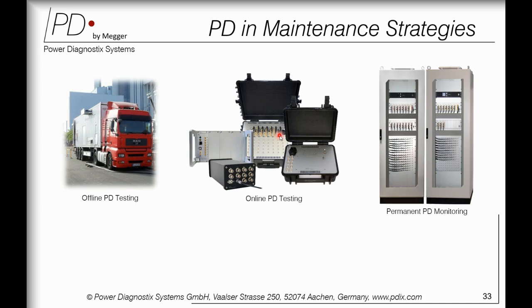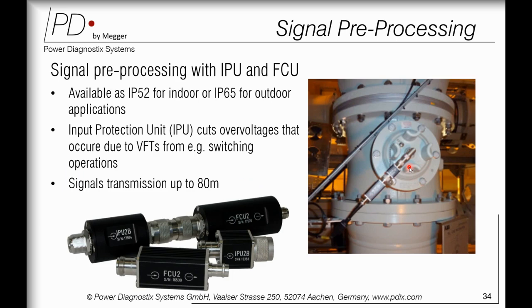Once your GIS is energized, it typically only follows online PD or the PD monitoring system. When we do PD measurement of GIS, whether portable or online monitoring, we always place an IPU and an FCU. IPU stands for Input Protection Unit. If any voltage surge is generated in the GIS due to switching, you may experience very high voltage on your UHF sensor outputs. To protect against this, we use the IPU. Second is the FCU, a frequency converter unit. Whatever frequency you are getting is converted to less than 1 megahertz as per IEC standards, and it gives you signal transmission capability up to 80 meters.